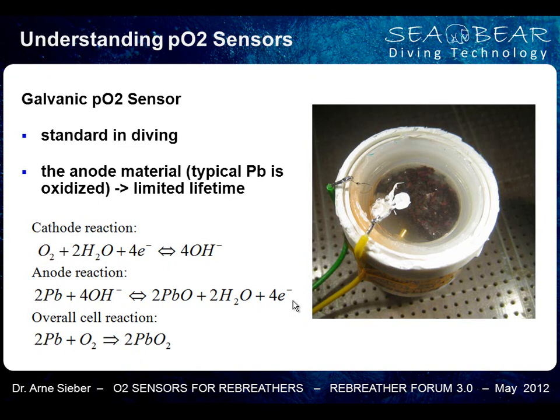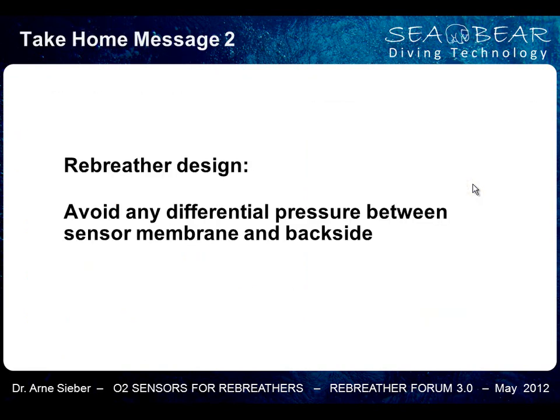If you look at this sensor, you see the lead below, and there is some reflecting light, and there is a membrane above that lead. Below, there is electrolyte and this lead anode, but there is a membrane above that, and that membrane is there to allow pressure equalization. This is very important in order not to get false readings. So here comes take-home message number 2, and this is especially addressing rebreather manufacturers and home builders. Avoid any differential pressure between the sensor membrane and the backside, because if you have a differential pressure, you will see that in the signals.